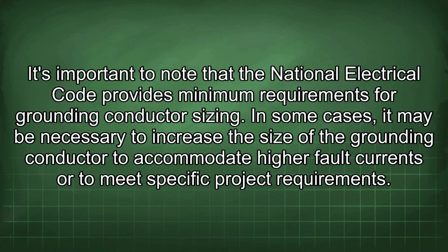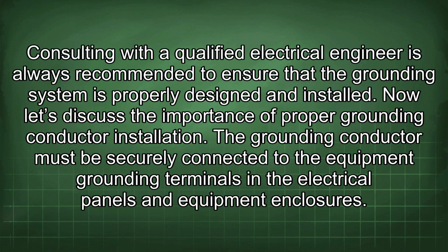It's important to note that the National Electrical Code provides minimum requirements for grounding conductor sizing. In some cases, it may be necessary to increase the size of the grounding conductor to accommodate higher fault currents or to meet specific project requirements. Consulting with a qualified electrical engineer is always recommended to ensure that the grounding system is properly designed and installed.